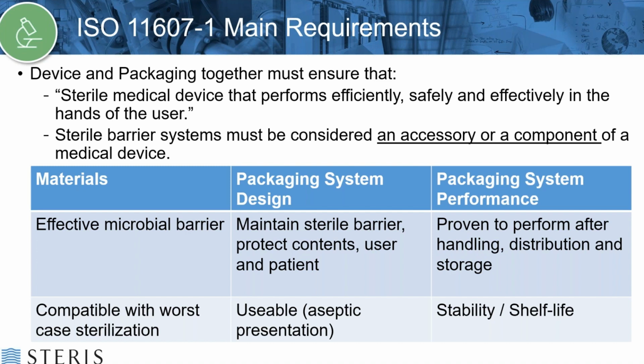And you need to make sure that those materials are compatible with worst case sterilization. So if it's going through a radiation sterilization method, the maximum dose that your product might see during routine processing. If it's going through a gas-based sterilization like ethylene oxide or steam, it has to be compatible with multiple sterilization cycles that you might want to consider validating during your sterilization validation.